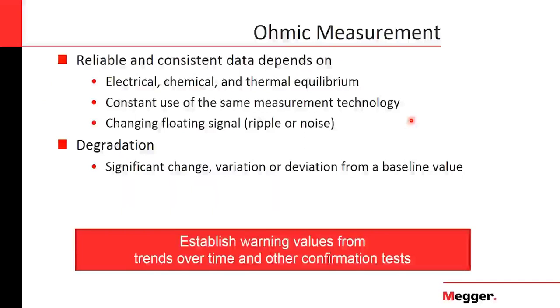To obtain reliable and consistent data, you depend on electrical, chemical, and thermal equilibrium. Basically, the battery has to be fully charged, and this is highlighted in another slide because it's really important to have the battery fully charged. But it has to be under floating conditions for 72 hours after running a full charge or running an equalizing charge, just to obtain this equilibrium. No changes in temperature, a stable temperature, no changes in the current that is used to charge the battery, no changes in the voltage. It has to be pretty stable and fully charged. And that's why the standards recommend 72 hours after adding water or charging the battery in the case of one type or another type of battery.